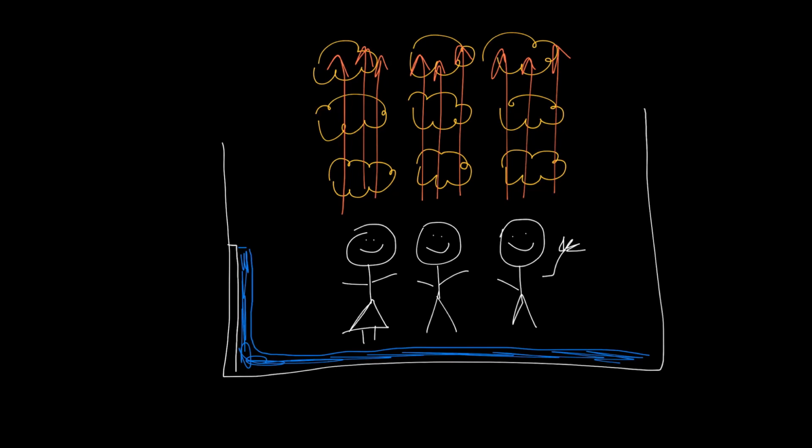As Mother Nature hates a vacuum, air from the supply air reservoir at the floor is drawn up to replace the rising heat plumes. This cool conditioned air not only conditions the students, but also serves as their source for inhalation. When they exhale, that air is warmer than the ambient temperature around them and gets caught up with the rising heat plumes, removing their respiratory contaminants with them. As such, the transmission of respiratory contaminants throughout the occupied space is minimized.